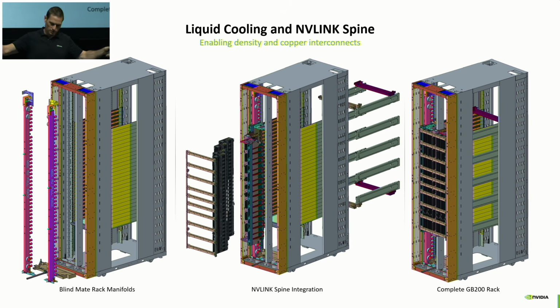We start with this tube, then we weld a lot of mechanical mounting points and alignment features onto it. The ports for the actual QDs are welded on there. When you weld something together, you introduce a lot of heat, and that heat creates a curve in the manifold, which is meaningful across that very long span.